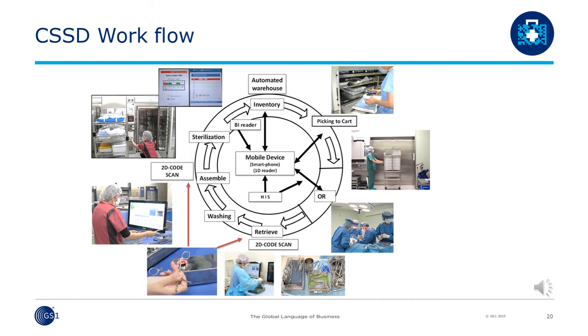Step 6. Picking. As per the surgery linked to the hospital information system, we load the sterilized items for each patient into the operation cart. We call it picking. A record must be made of the dispatch of any item from this area, and stock is issued on a first-in first-out basis. Step 7. Delivery. The surgical cart is taken to the appropriate operating room according to the surgical schedule. In this work, GLN is used to respond to sudden changes in the operating room.